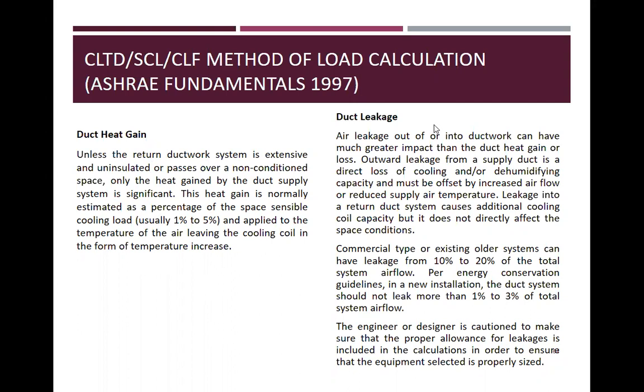Okay? Duct leakage. Air leakage out of or into ductwork can have much greater impact than the duct heat gain or loss. Outward leakage from a supply duct is a direct loss of cooling and/or dehumidifying capacity and must be offset by increased airflow or reduced supply air temperature. Leakage into a return duct system causes additional cooling coil load, but it does not directly affect the space condition. Commercial-type or existing older systems can have leakage of 10 to 20% of the total system airflow.